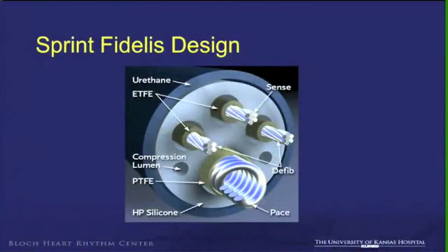So this is the overall design. I won't go into the details, but you see it's not a coaxial lead, which is the change in the pattern of lead design over the last decade. Earlier leads were coaxial, and now they're not coaxial.